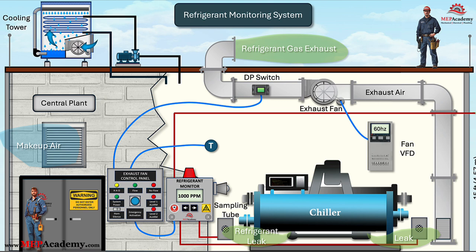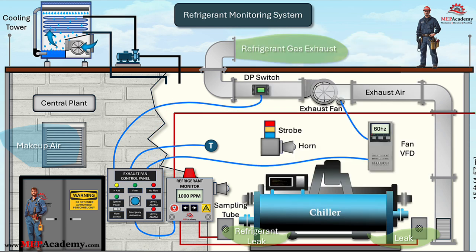The controller sends an analog signal to the fan's VFD to increase the fan's speed as programmed. There will also be a digital signal for starting and stopping the fan. If the refrigerant leak reaches level 2 values in the space, the refrigerant monitor sends a digital signal to activate the audio and visual alarms inside the chiller room and outside at the entrance to the room per ASHRAE 15 8.11.2.1. The exhaust fan requires a break glass on-only control switch located immediately outside the chiller room door to ensure emergency ventilation in the event of a refrigerant leak.